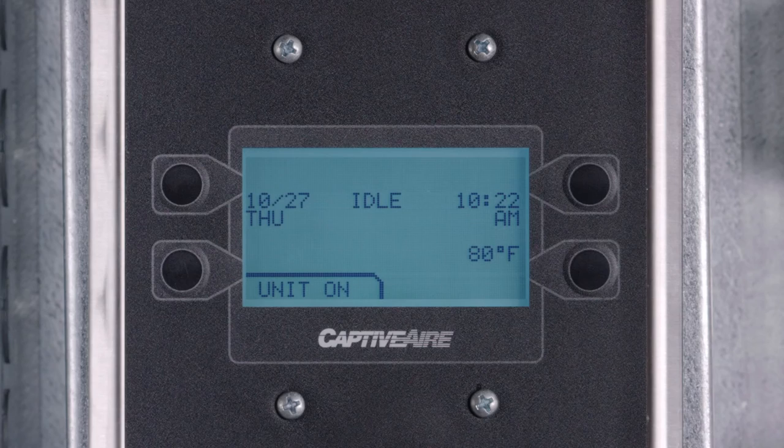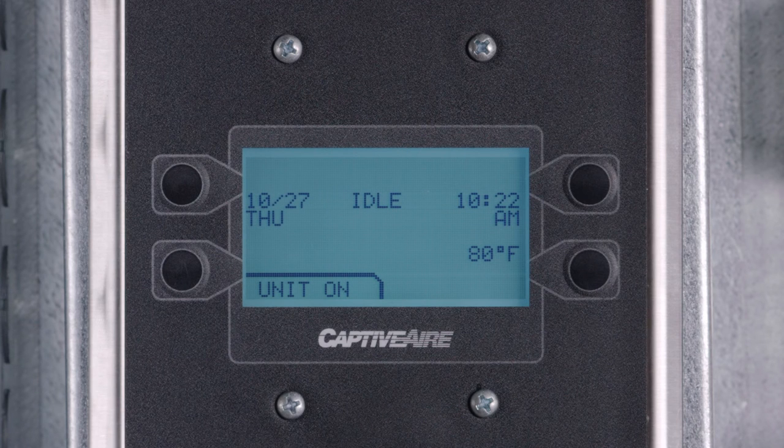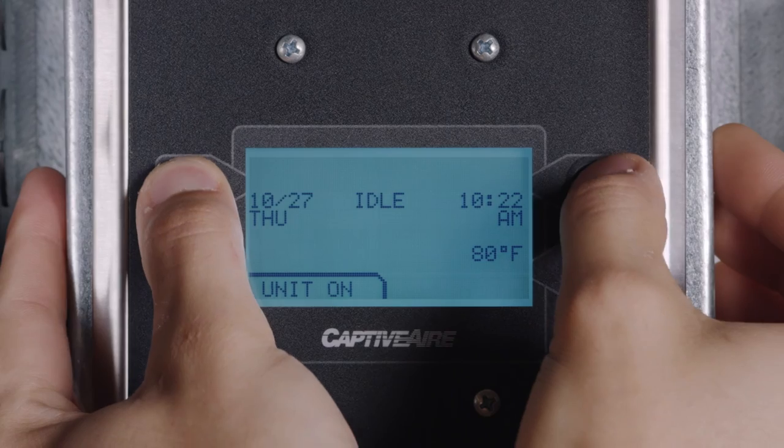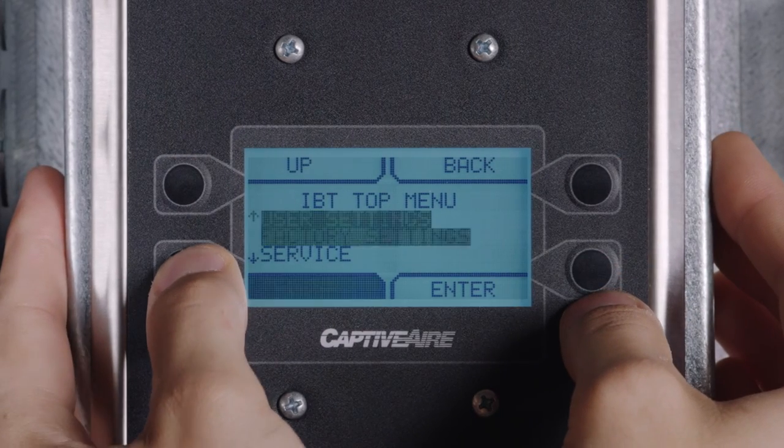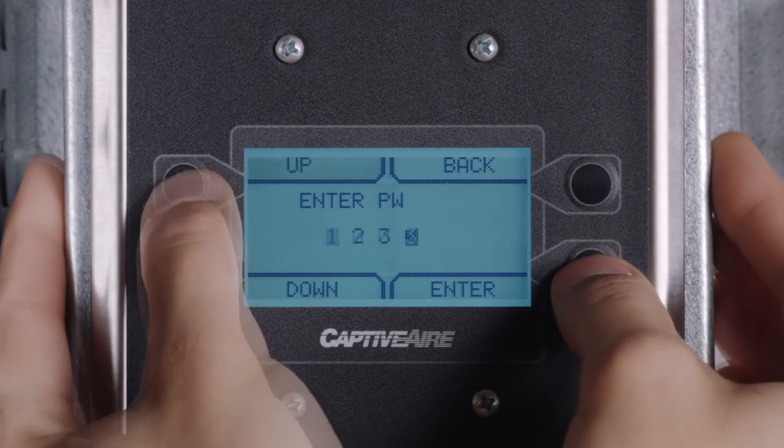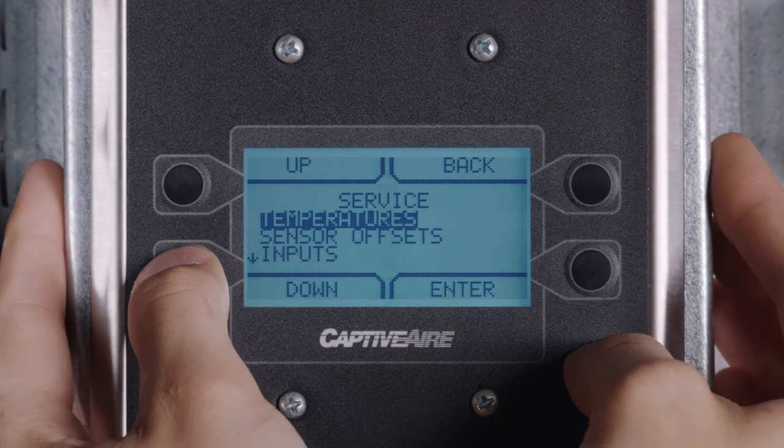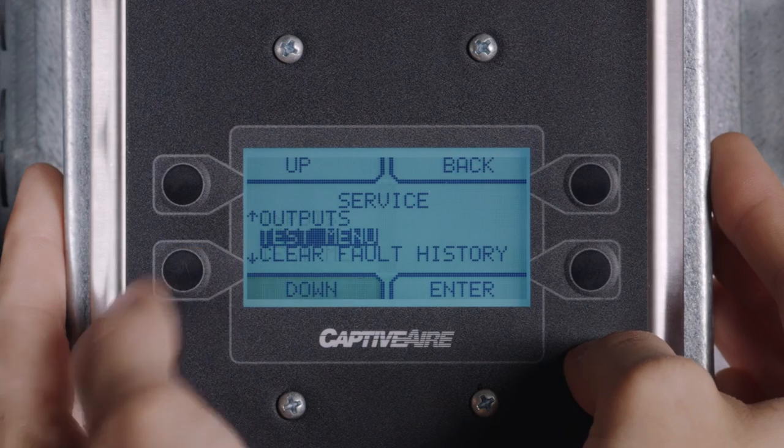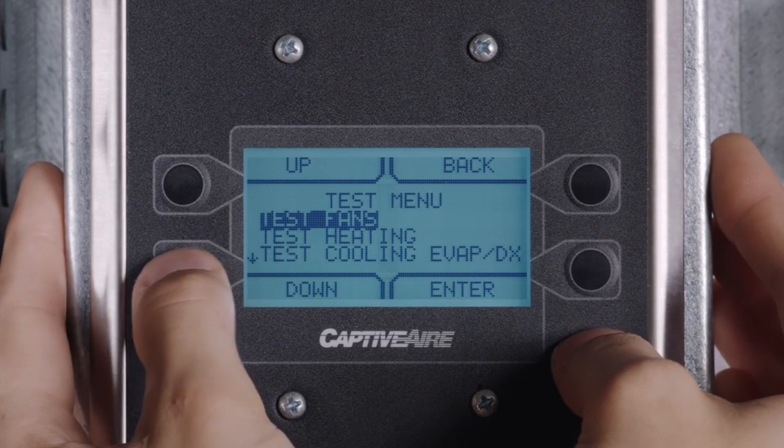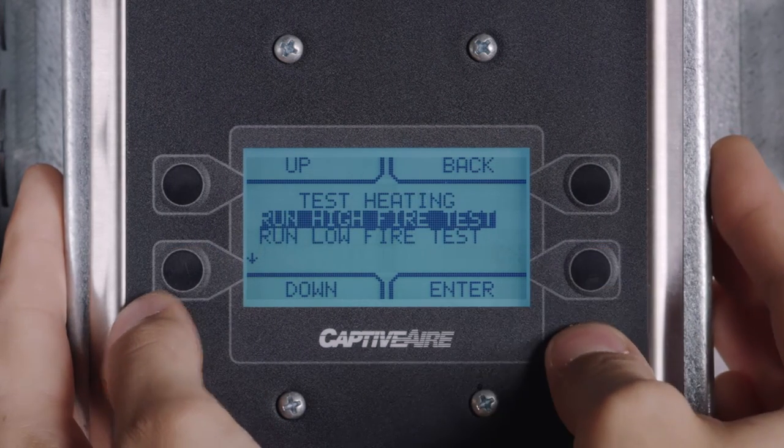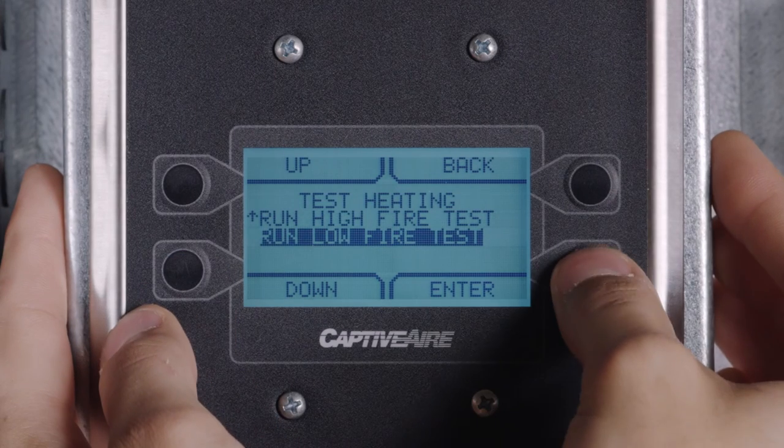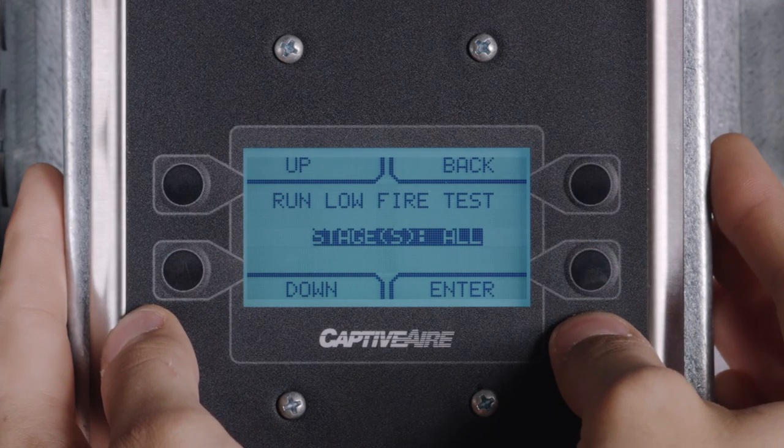Next, the low fire gas pressure needs to be adjusted. From the main screen on the HMI, first access the menu. Then select service. Enter the password 1234. Select test menu. Test heating. Run low fire test. All stages.